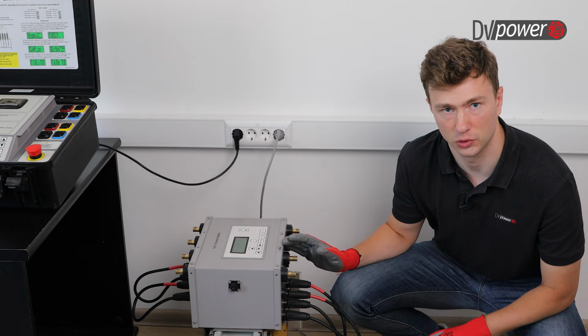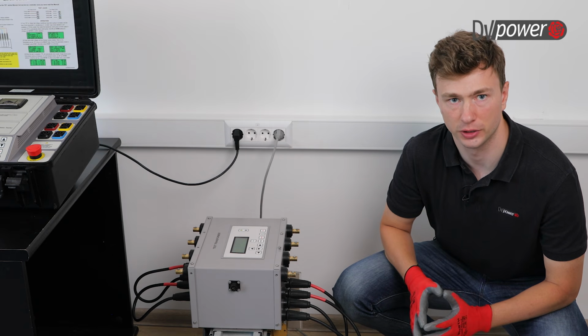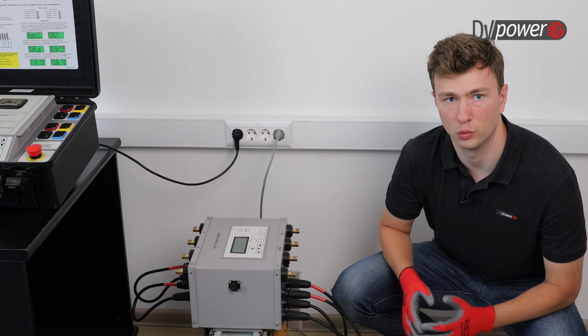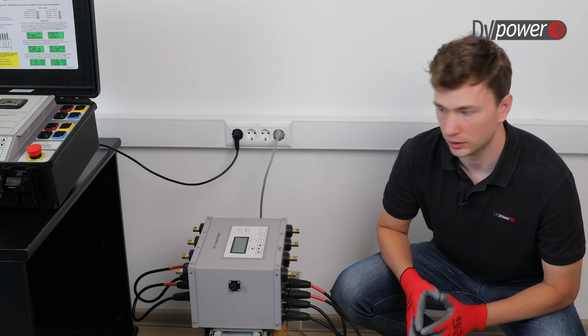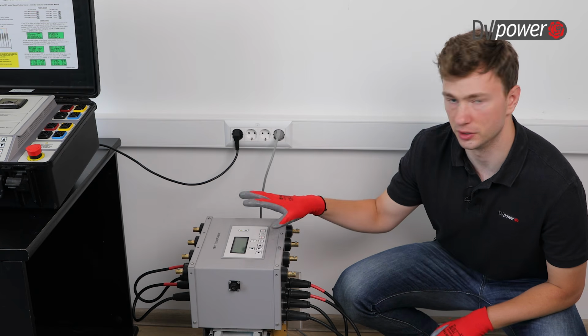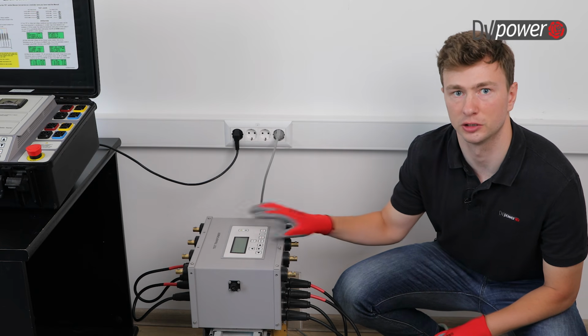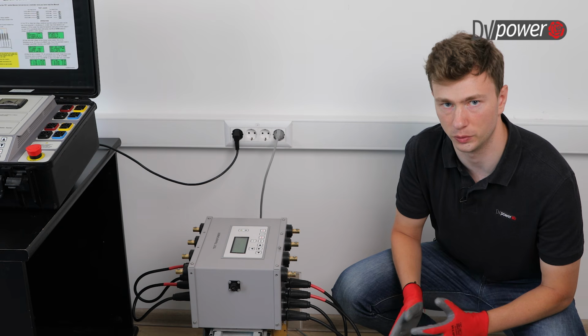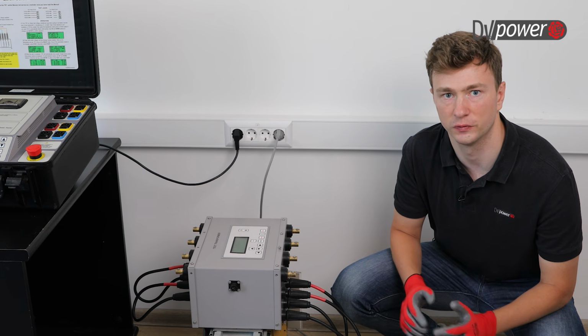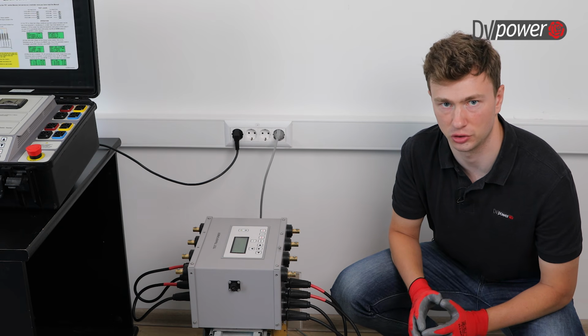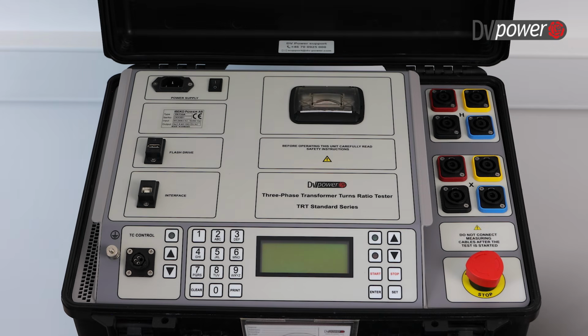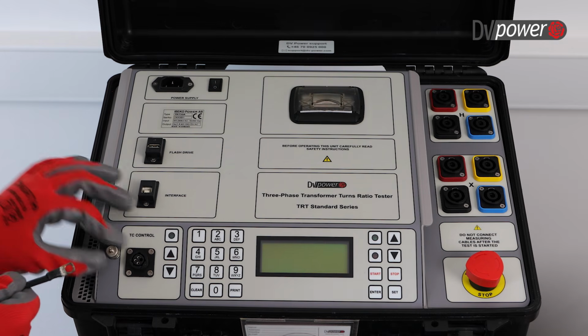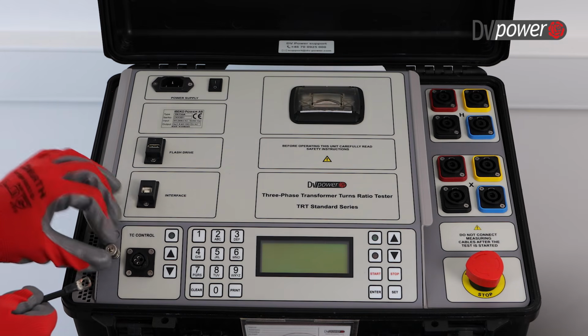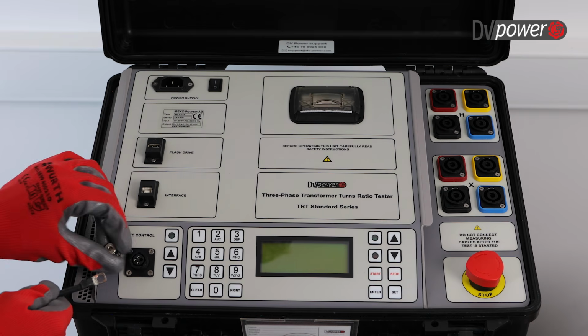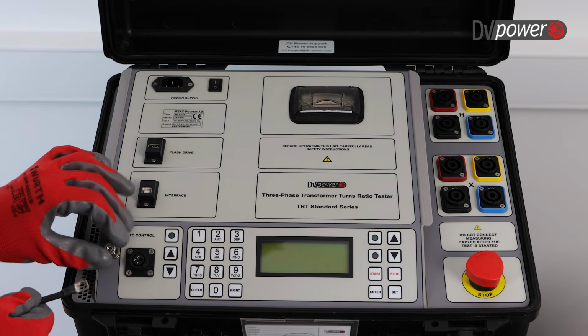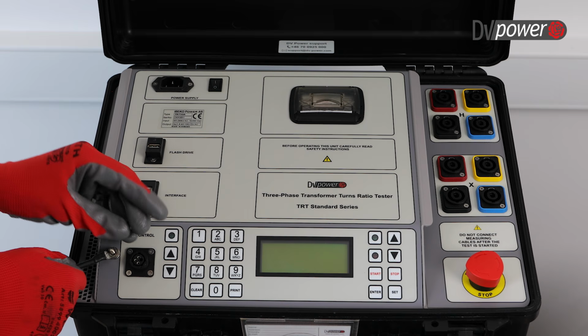This is our test object, a 3-phase transformer with a vector group YN0, and on top of the transformer there is a tap changer simulator which enables us to perform tests on up to 5 tap positions. Firstly, we connect the grounding cable to this port, as already explained. We need to think about our safety and the safety of our equipment first.